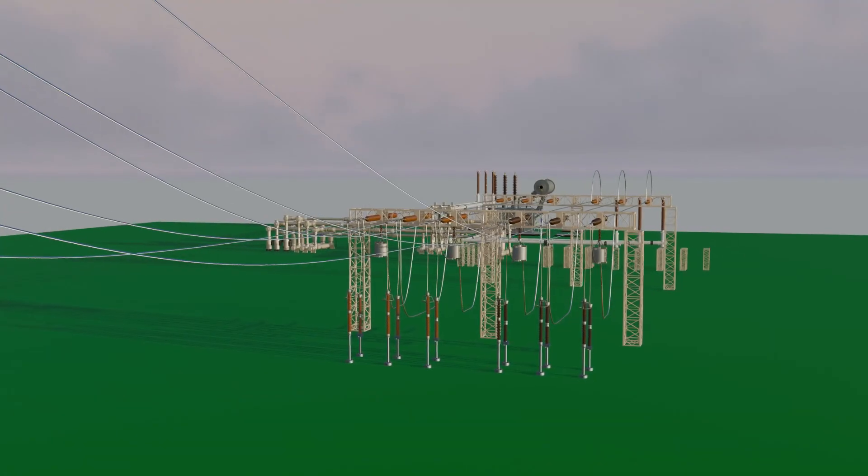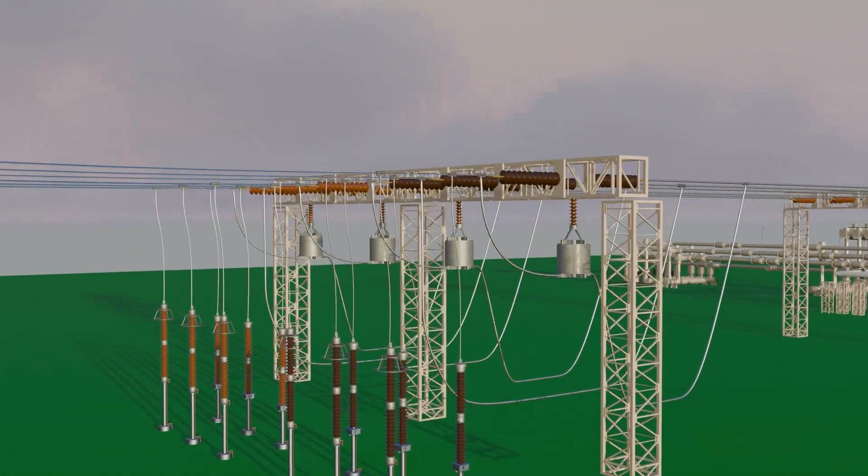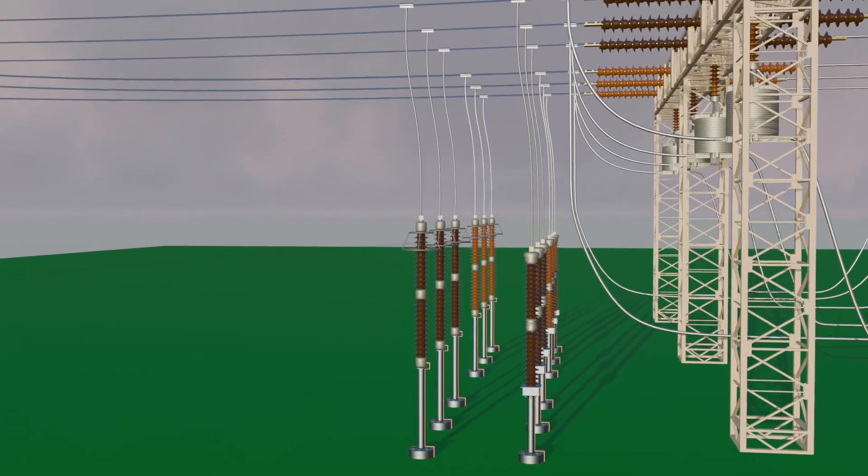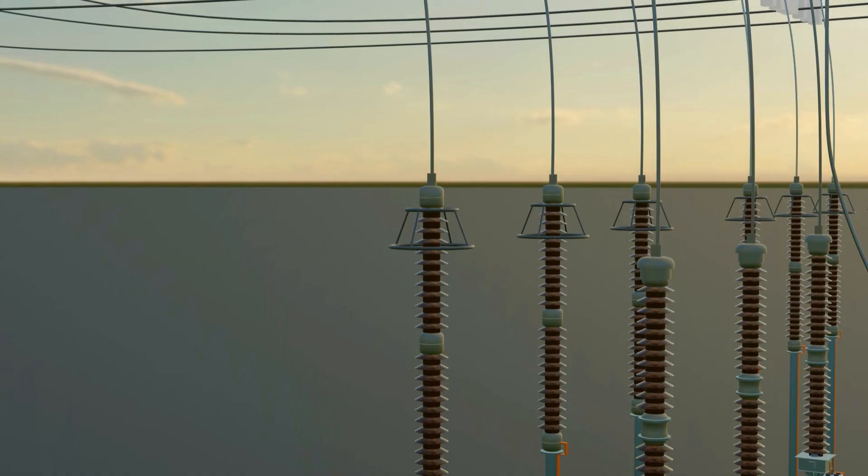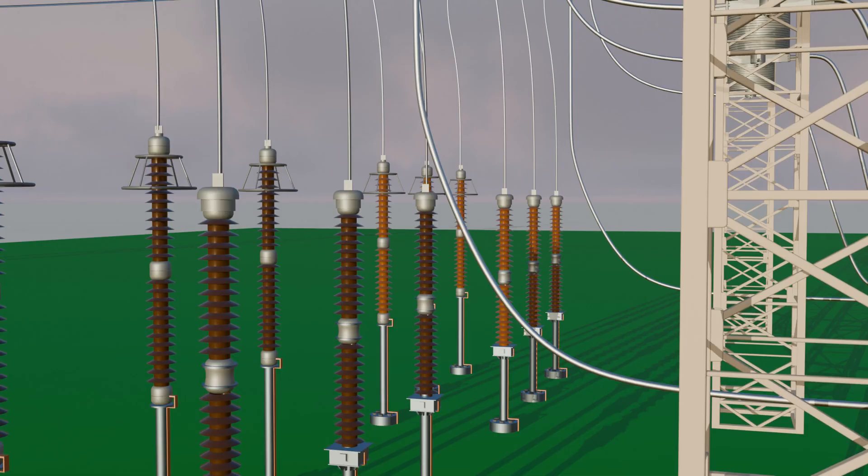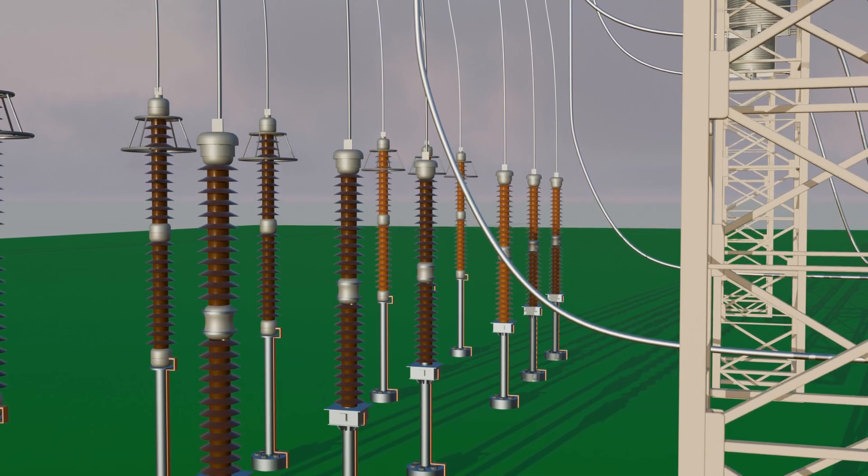Here a 400 kV transmission line is arriving and is terminated on a gantry tower. The first device connected here is a lightning arrestor. It provides a low resistant path for lightning strikes and overvoltage surges on the line, so the excess energy is safely diverted to earth. Next comes the CVT, the capacitive voltage transformer, which measures high voltage.